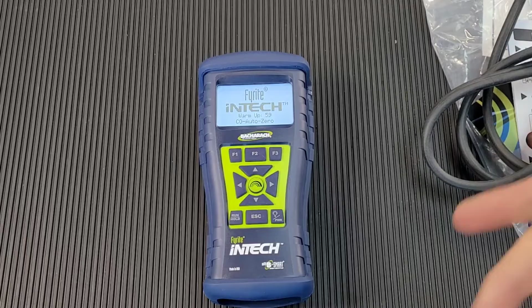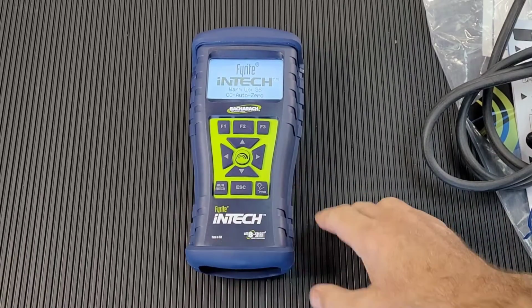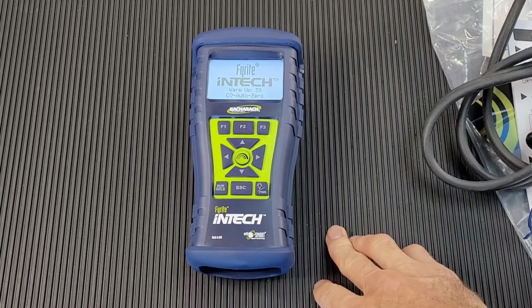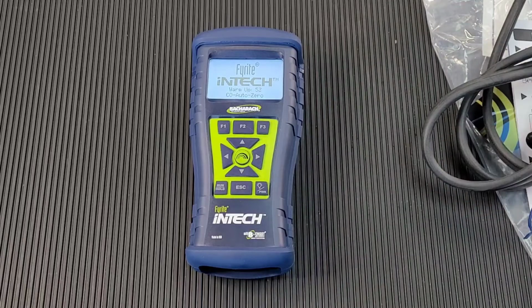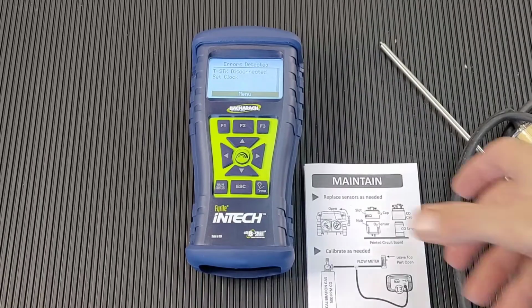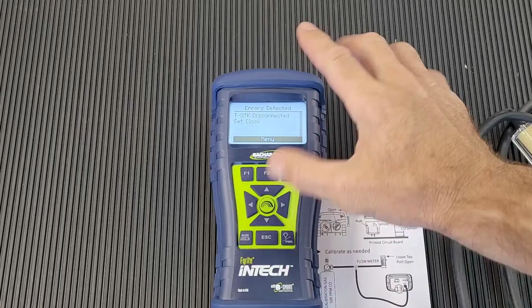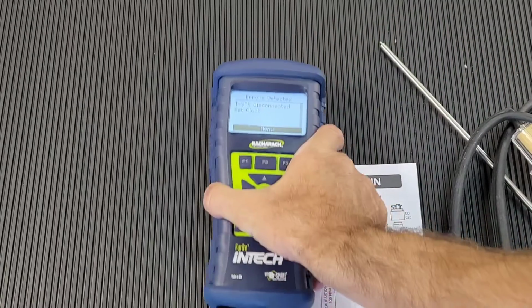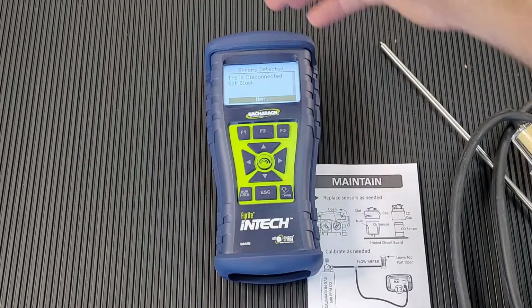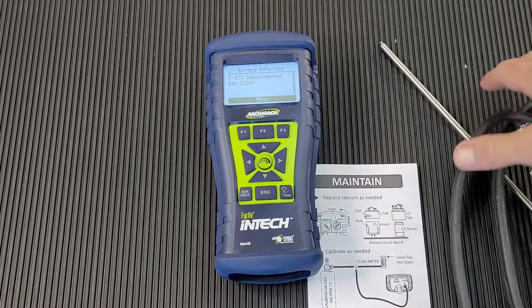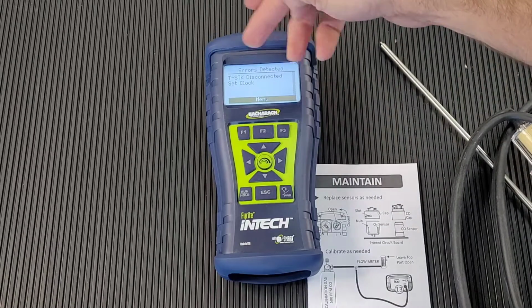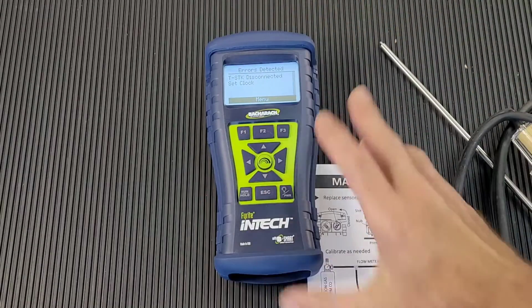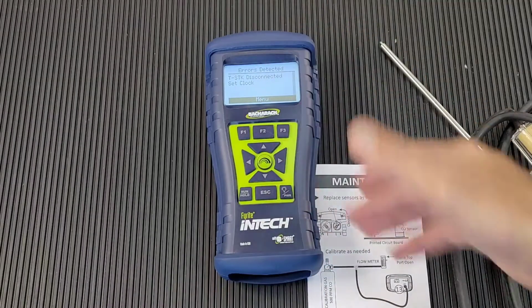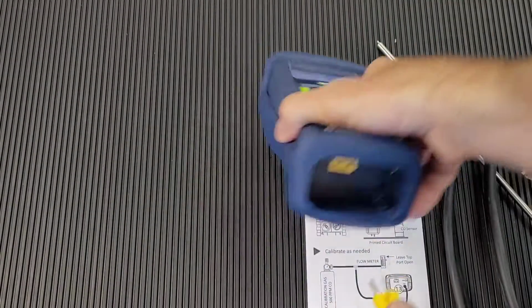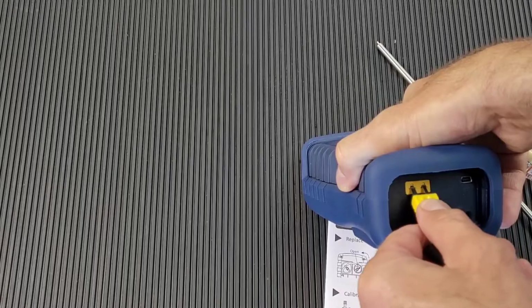Okay, it goes through a 60-second warm up, and we will come back once that's going. Okay, folks, we just got the countdown down, and as you saw, we got the start up, and we're getting errors. So this is basically saying the thermocouple is disconnected and set clock. So that's what you see if you don't connect things. Okay, I'm going to connect it up right now. Let's go for it, and then we'll see what happens to the errors.